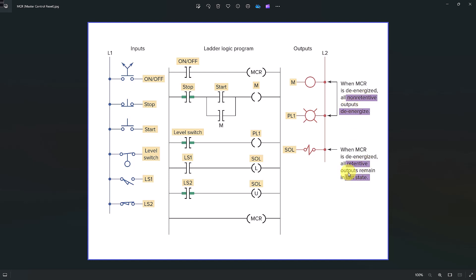As for the retentive output — the output that holds the last value — for example, this latching/unlatching virtual coil. L is latching, U is unlatching. When this virtual latching output coil is energized, it will latch the value and hold the on state. Once energized, it will continue to remain energized because there is an L here — it will latch and continue to hold.